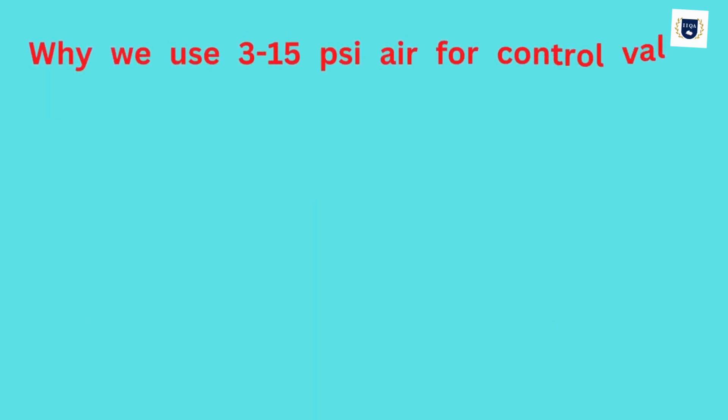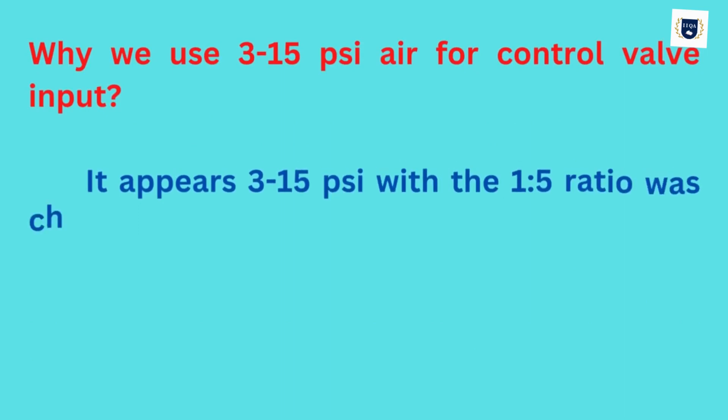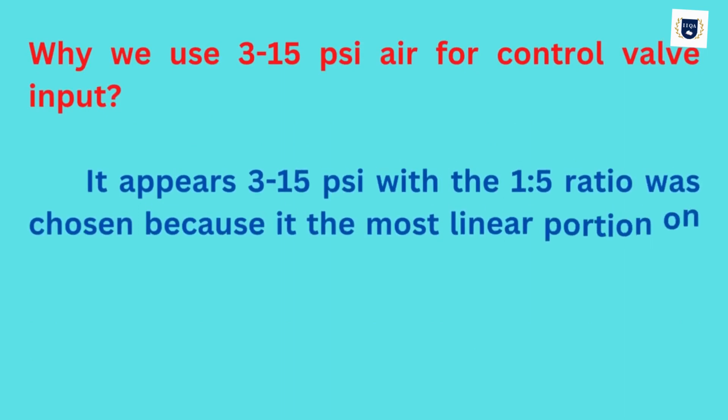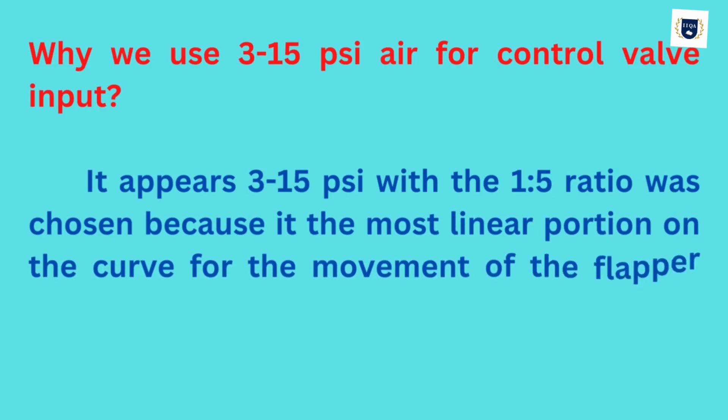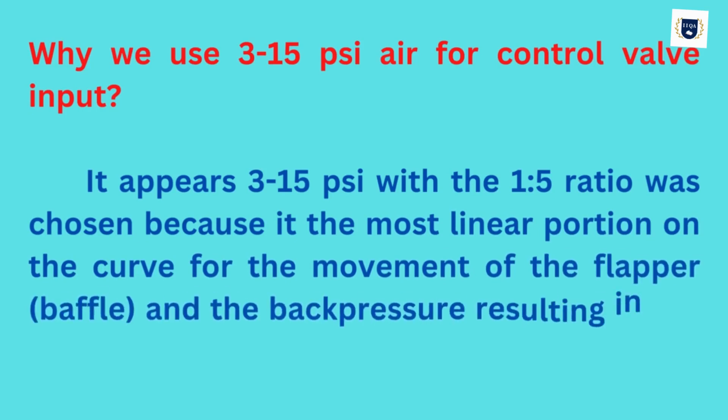Why do we use 3 to 15 psi? Air for control valve input - it appears 3 to 15 psi with the 1 to 5 ratio was chosen because it's the most linear portion on the curve for the movement of the flapper, baffle, and the back pressure resulting in the nozzle.